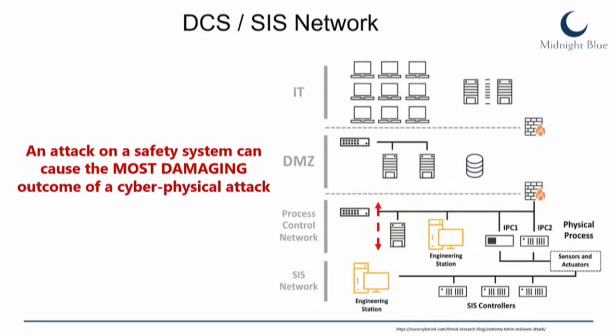Safety instrumented systems are software systems, and because they are a line of defense, it's typically recommended that they run on an isolated and segmented network. But for ease of design and maintenance, they're often connected together with the main control system, and that allows the attacker to obtain remote access to safety instrumented systems.